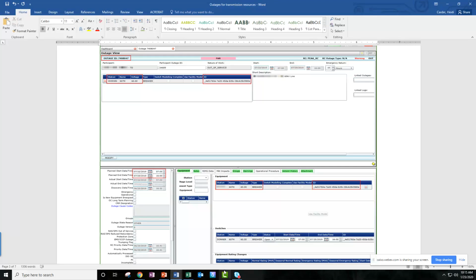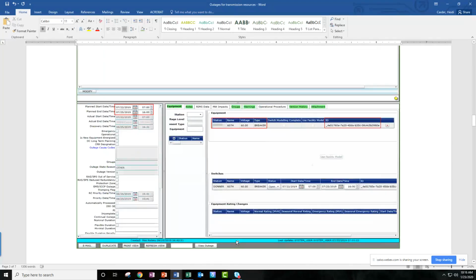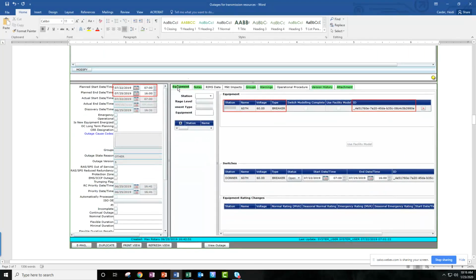Some common issues that we run into with the EIM operators, and we're going to dive into that a little bit, are the electrically disconnected generators. Just from a transmission standpoint, the switches that are modeled open, for example, that are normally closed, can have an impact not only to electrically connected generators, but also to your ratings on buses, lines, transformer banks, etc. So we want to make sure when you open the card, you can go into the equipment. It's a tab kind of in that second half of the section in the screenshot that you're viewing. There's an equipment tab, and when you click on that, then you can see any equipment that's associated and been modeled into the outage. And the switches that are modeled into the outage will supersede any telemetry.